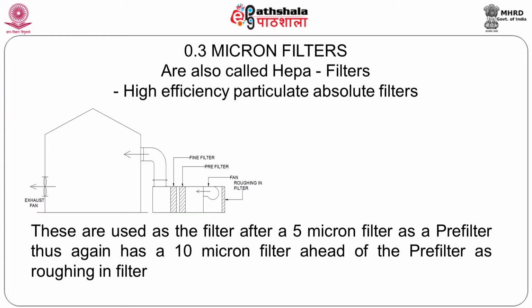Now in the earlier slide, you saw the HEPA filter, the fine filter, located in the air handling unit, right? It was in the machine. After the machine, you had a certain portion of the unit and some ducting. Now that portion of duct which is closest to the air conditioned space or a ventilated space will have access to the duct. So any dust, any vermin which might settle into the duct has a fair chance of getting into the air conditioned space.